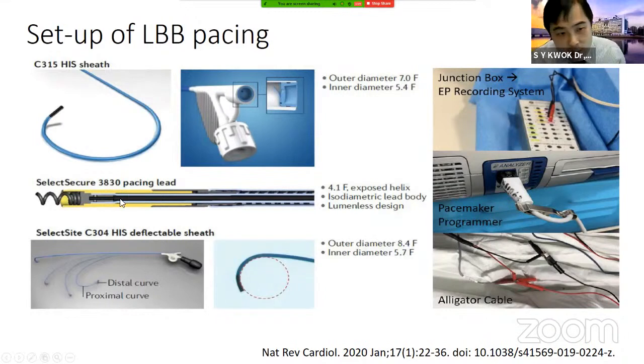First is the Select Secure 3830 pacing lead. This is a 4.1 French lead with a lumenless design. It also needs to be coupled with the long sheath. This is a specially designed C315 His sheath with an outer diameter of 7 French. And of course, the other alternative, which has a bigger diameter, is the 8.4 French C304 deflectable sheath that you can use with the Medtronic system.